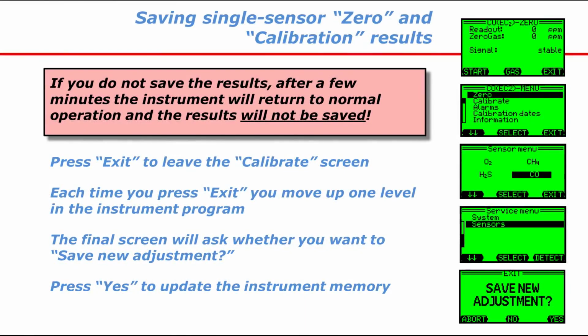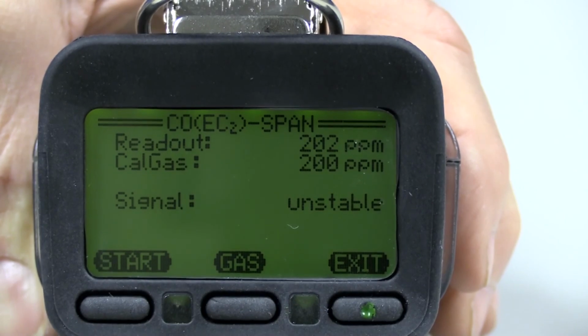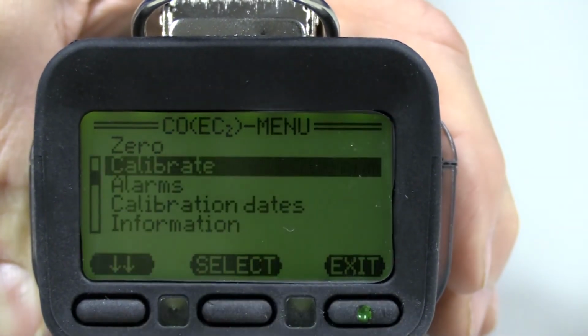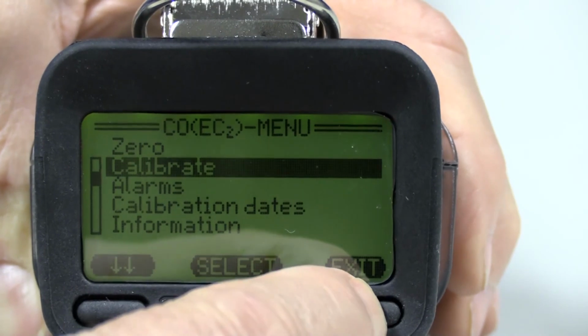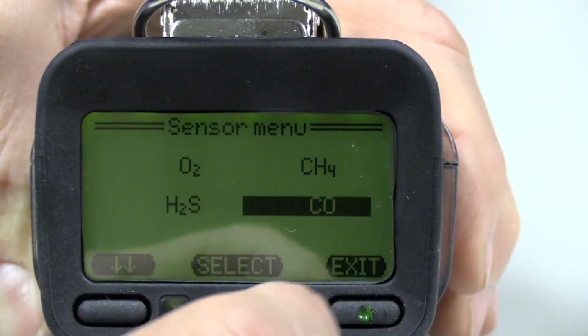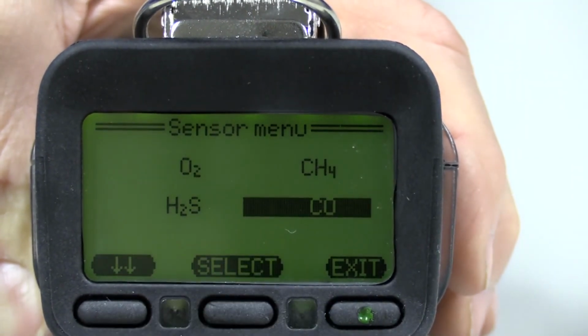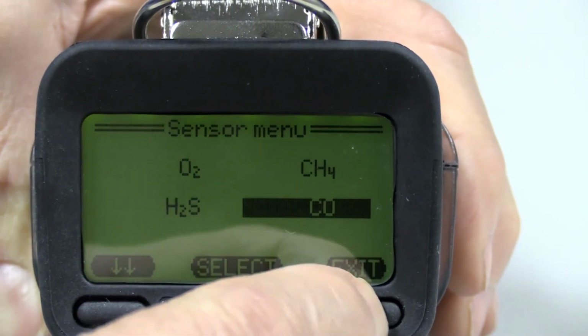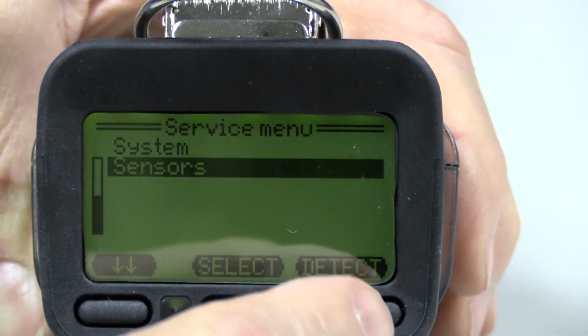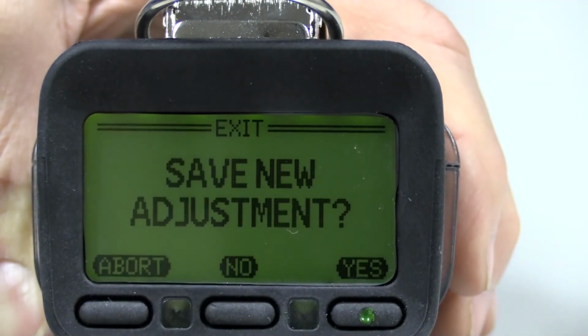The next step is very important. After successfully completing the single sensor calibration, you must update the instrument. To do this, press Exit. Each time you press exit, you go up one level in the menus. Press exit again as often as prompted, then detect to return to normal operation. The screen will ask, Save new adjustment. You must press Yes in order for the new information to be updated to the instrument memory.